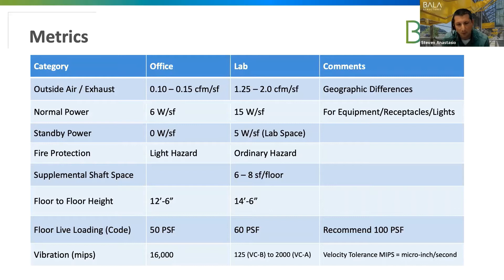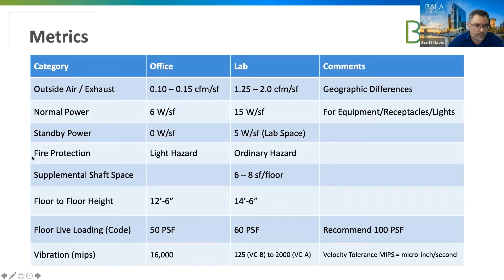And one other quick note to add for the vibration, in addition to or instead of maybe structural enhancements, the scientists themselves may be able to assist with anything that's vibration sensitive on their part. Essentially, this would only really work for benchtop equipment, but they may utilize what's called an air table, and essentially it's nothing more than a small air hockey table that sits on top of the bench, creates a bed of air, and then their sensitive equipment sits on top of that. And that will basically eliminate vibrations that may impact their sensitive equipment. So again, just to share a thought, even just dialogue with the client may be able to come up with a solution that doesn't require a lot of extra reinforcing. Again, it's really going to go back to the sensitivity of the equipment. Okay, next slide.